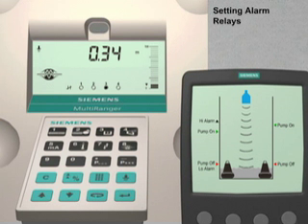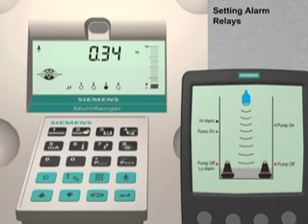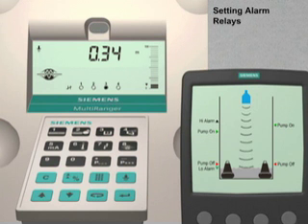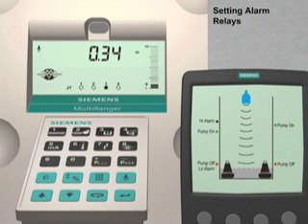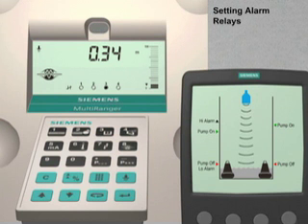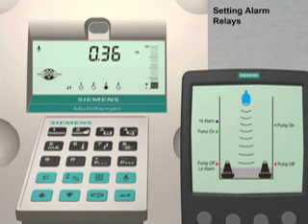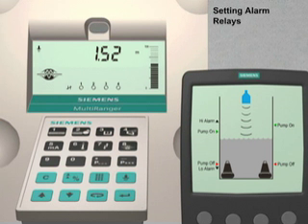You can see on the Multiranger display that the four relays are currently active. The current liquid level reading is 0.34 meters, which is below our low level alarm relay set point of 0.4 meters. The icon for relay number 3, the low level alarm, is in the closed state, meaning the low level alarm is on. As the liquid level rises, the low level alarm will turn off. As the liquid continues to rise, pump number 1 will turn on, which slows down the vessel filling rate, but the liquid level continues to rise.